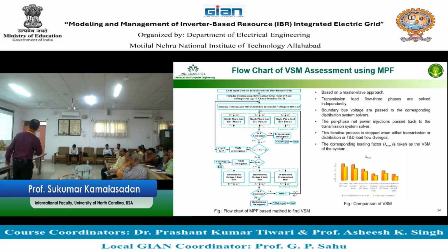If you do all the studies, end of the day you say, hey, this distribution system I know it's very unbalanced, and phases are different. And I cannot load beyond 1, meaning I cannot load beyond the current situation. Don't load beyond the 1, because if you do, it will collapse. So that is something the tool can be used to predict. Otherwise, you don't know how the distribution network is connected, and you go and then connect.